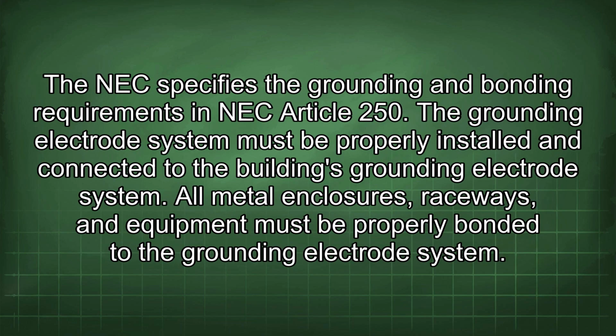The NEC specifies the grounding and bonding requirements in NEC Article 250. The grounding electrode system must be properly installed and connected to the building's grounding electrode system. All metal enclosures, raceways, and equipment must be properly bonded to the grounding electrode system.